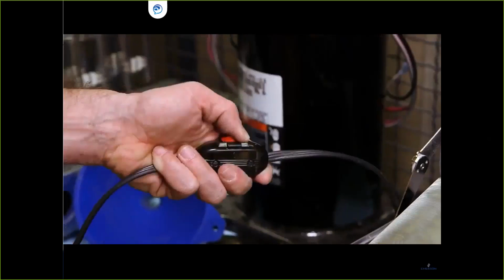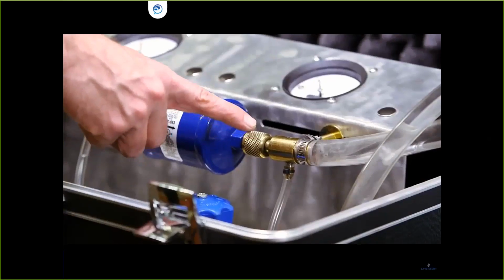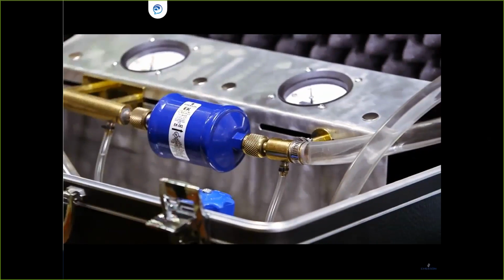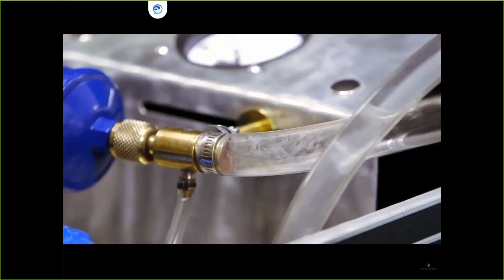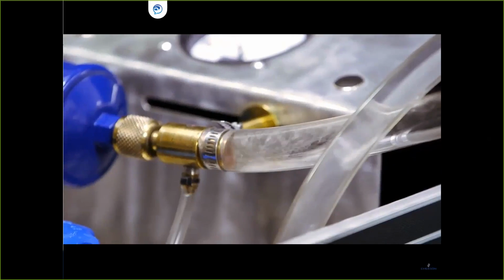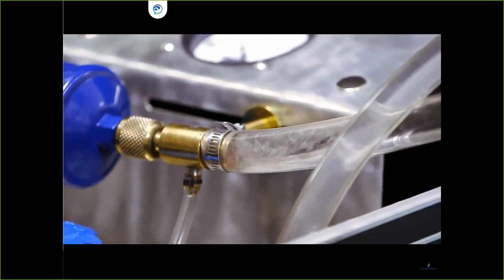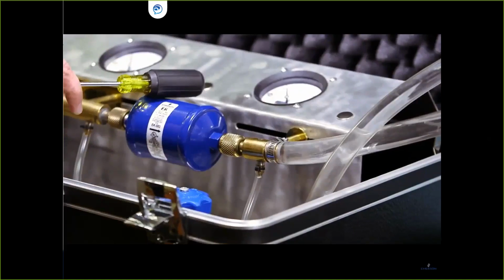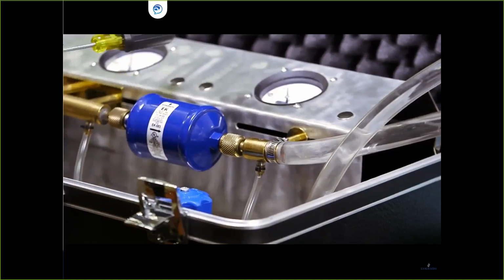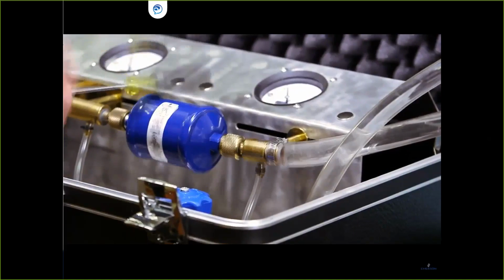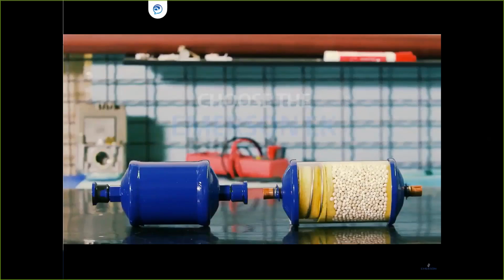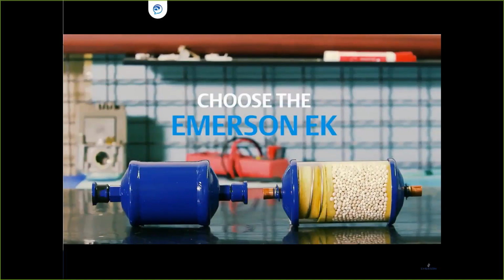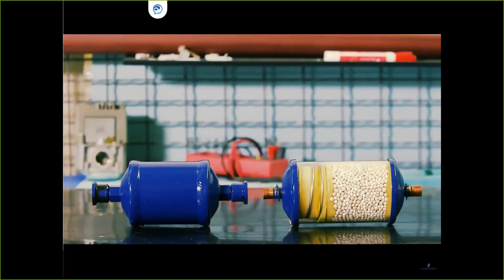When we start and stop the pump to mimic system cycling, the outlet line of the dryer remains clear, demonstrating that the EK filter dryer continues to hold the contaminants. By tapping on the Emerson EK, we simulate system vibration. Once again, the line remains clear, showing that the filter dryer is retaining the contaminants. For best-in-class 20-micron filtration, choose the Emerson Compacted Bead Liquid Line Filter Dryer.